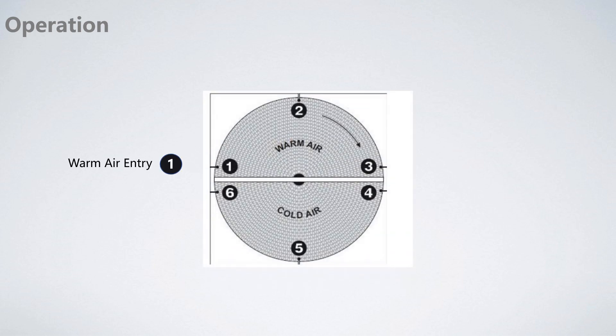And then how it works. The first step is warm air entry. The wheel rotating at a speed, and the air channel has entered from the cold air into the warm air. The storage mass has been cooled down nearly to the cold air temperature. The second step is mid warm air. This air channel has already passed half of its time in the warm air. The channel temperature is about the same on the inlet side and on the outlet side.